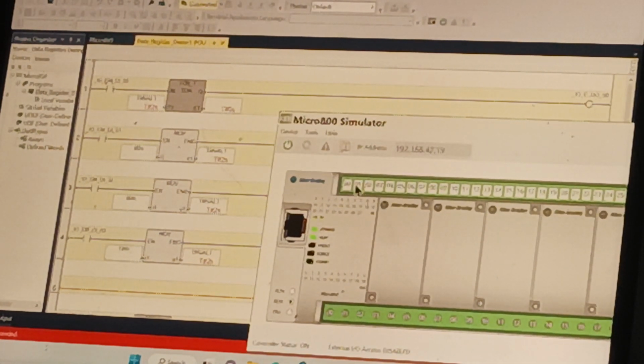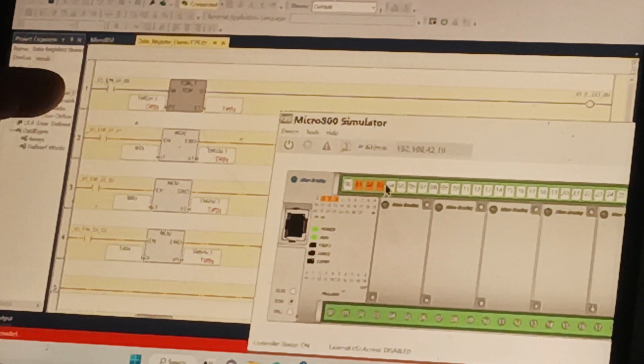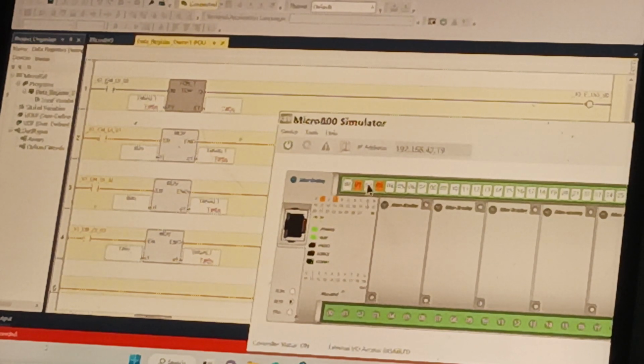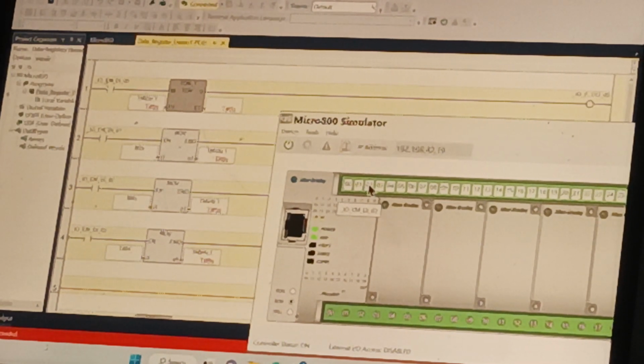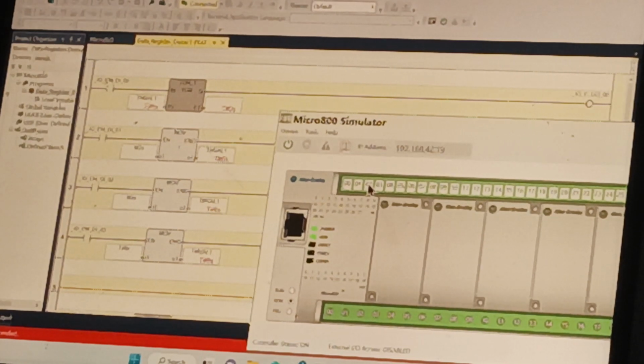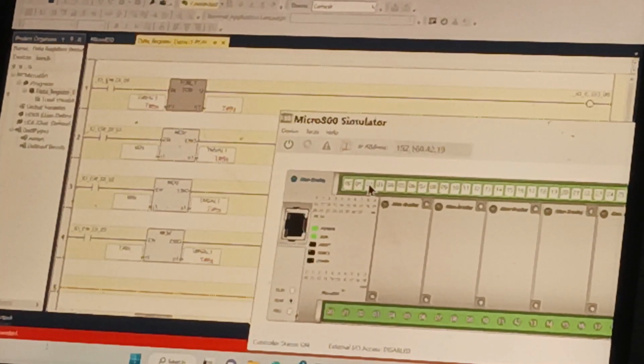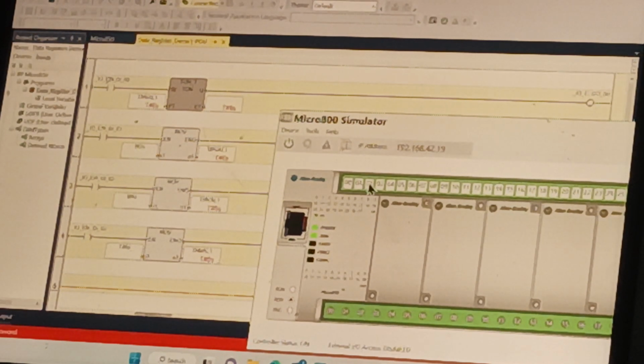And just like the move function on the Delta, if I were to have them all stuck on 1, 2, and 3, it stays at 6 seconds, right? I can turn off 2, 1, it still stays at 6 seconds. I turn off 3. I mean, the bottom line is, we don't want these on toggle switches because then something will be left on, and if more than one of these move inputs are on, it just goes with the highest value. So sometimes people will try to turn something on and wonder why it isn't moving, because you have a higher value that's still on. So I put these with momentary push buttons.